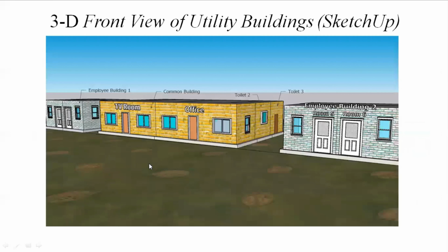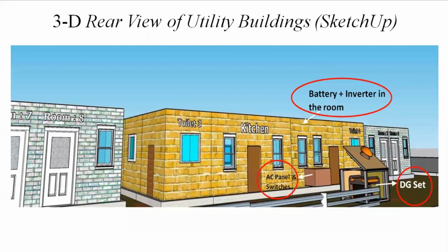This is an image showing a 3D front view of the utility buildings, which we have just put together from our SketchUp 3D model. This is a 3D rear view of the utility buildings, and the diesel generator set is decided to be put just behind this battery inverter room so that wiring cost is reduced, and the AC panel and switches will be carried by this box. And as I discussed, this small room has 2 windows, and we have also decided to put all our ground mounted panels at a 30-degree tilt angle and 20-degree azimuth, and we will put those panels just behind this utility building.